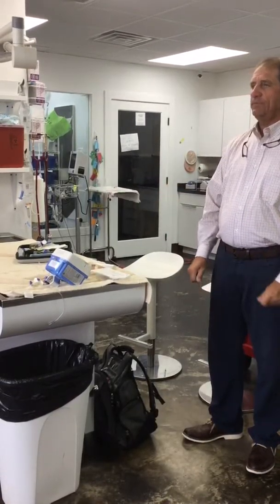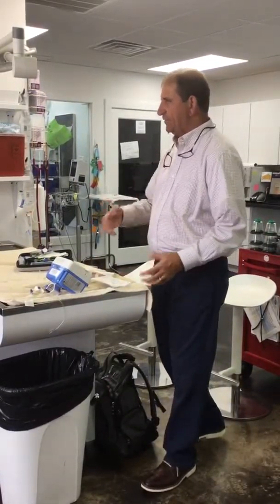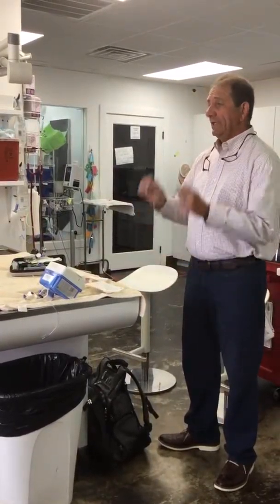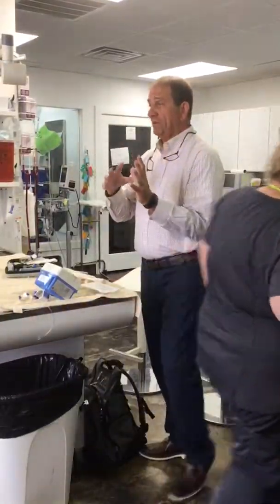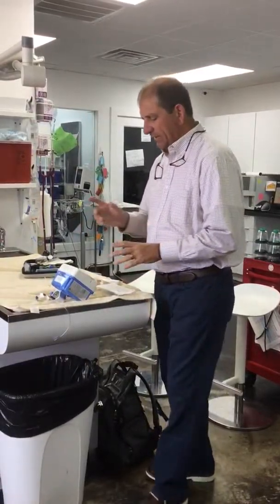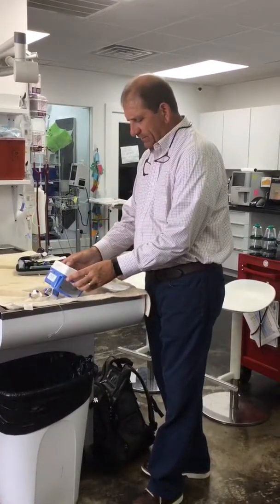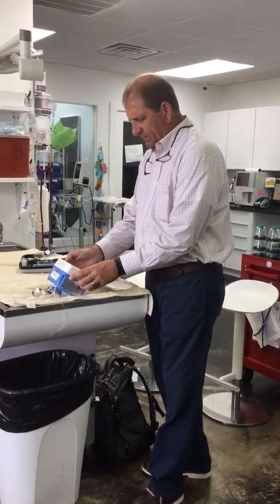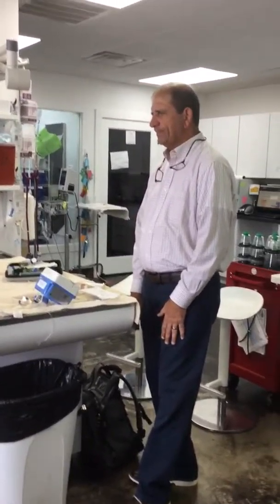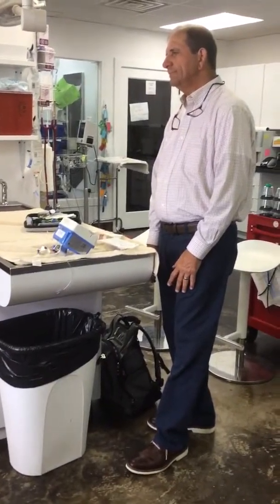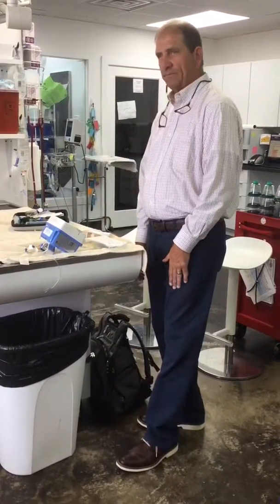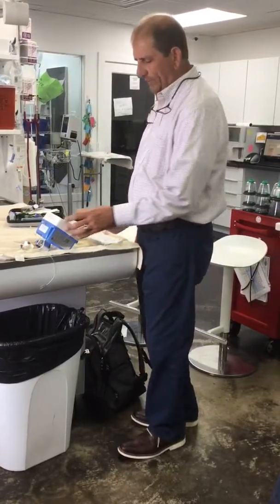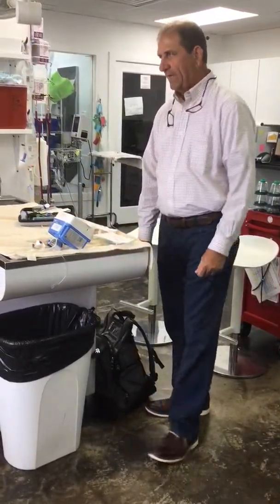Okay. So if you feel like your pump is not accurate, you call me and I would say press that load button and look at that number. If it's 5% off one way or the other, then we'll recalibrate it. It's just real simple. Now I want you to go back, and this is the last thing. Go back until you see the tube, T-U-B-E. All right, you see it? Yes. All right, click tube for me. What does it say? Tube A. Tube A. I calibrated tube A. And tube A is, for us, the 10 drop, the Baxter sets. Okay, so that's what's calibrated.